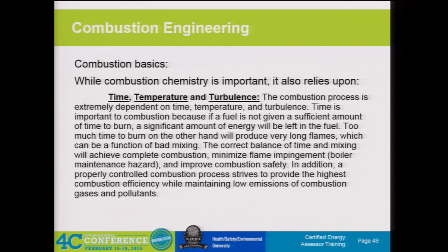The turbulence is that mixing energy to make sure that our air and fuel is being introduced appropriately—that the oxygen is there at the time we need it to enhance the combustion. And obviously the temperature control: we want to make sure we're controlling our process so that we're extracting temperature and controlling that temperature inside the firebox to make sure we're supporting combustion but not getting too much temperature in the unit.